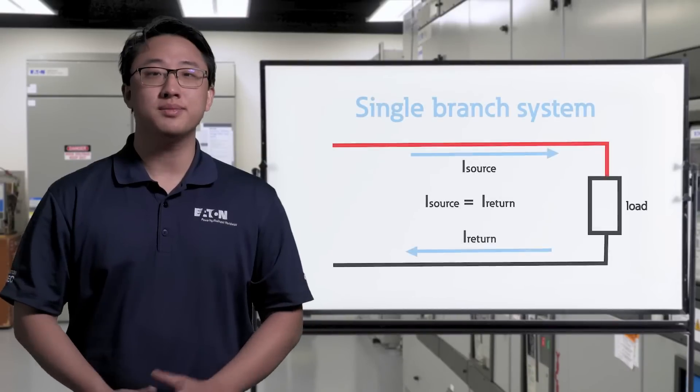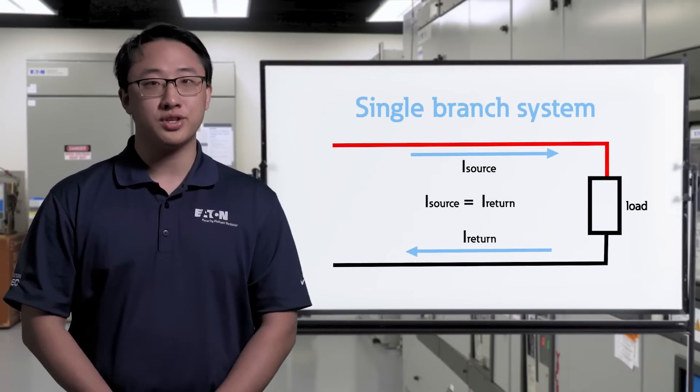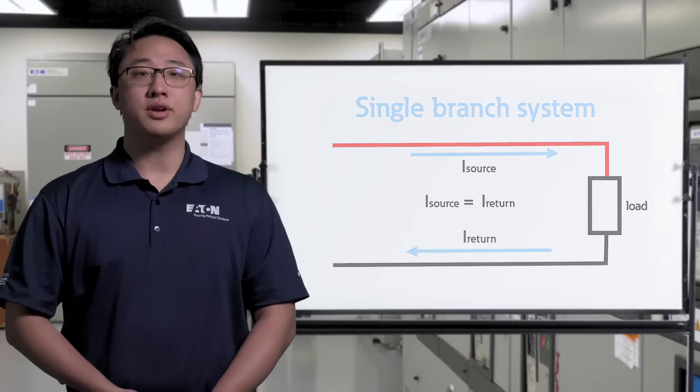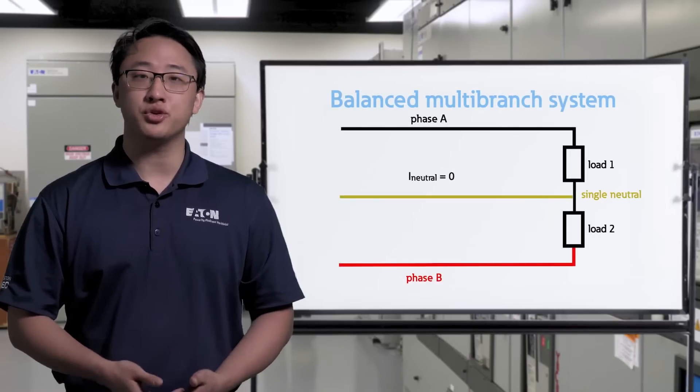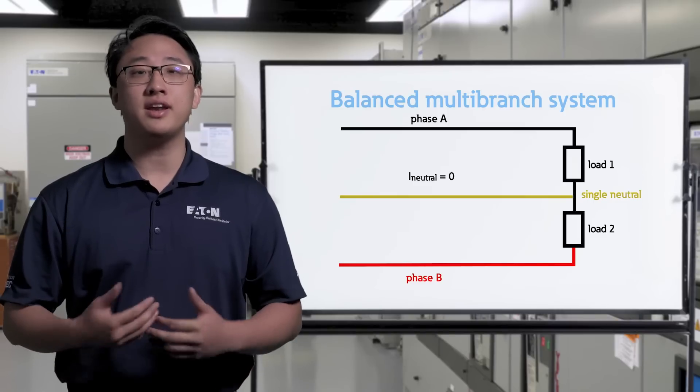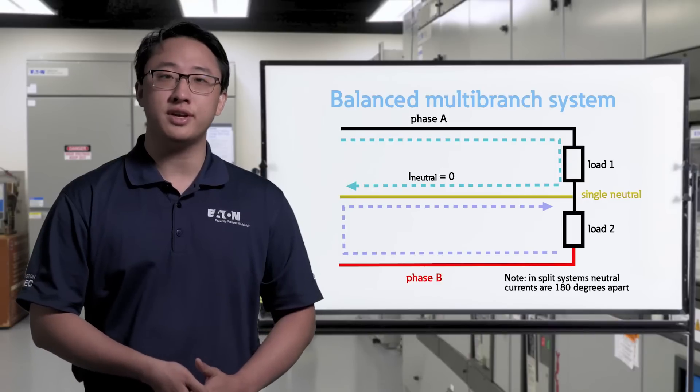In a single branch system, or a system where each phase has its own neutral, the neutral wire will carry all of the return current just like we expect. However, in a balanced multi-branch system, or a system where multiple phases share a single neutral, the neutral actually won't have any current. Instead, the current will return on the other phases which are at complementary points in their cycle.